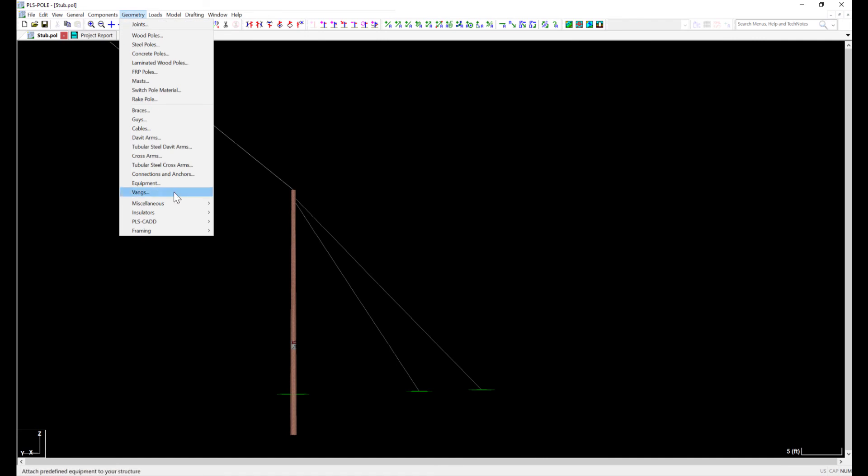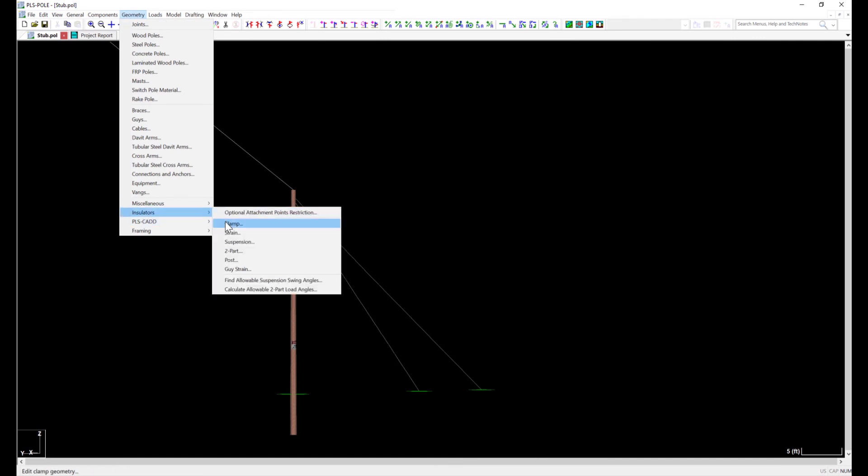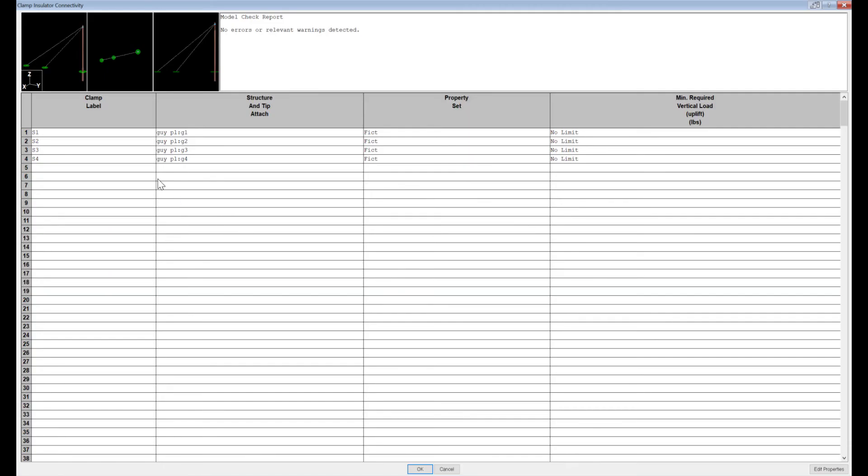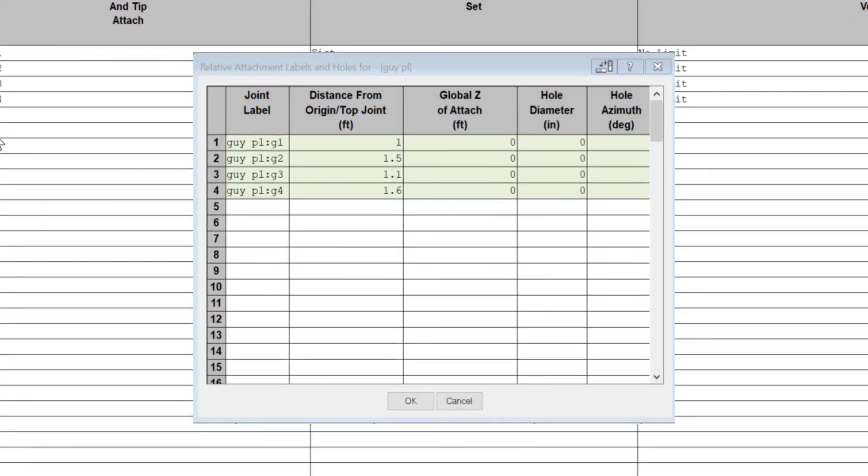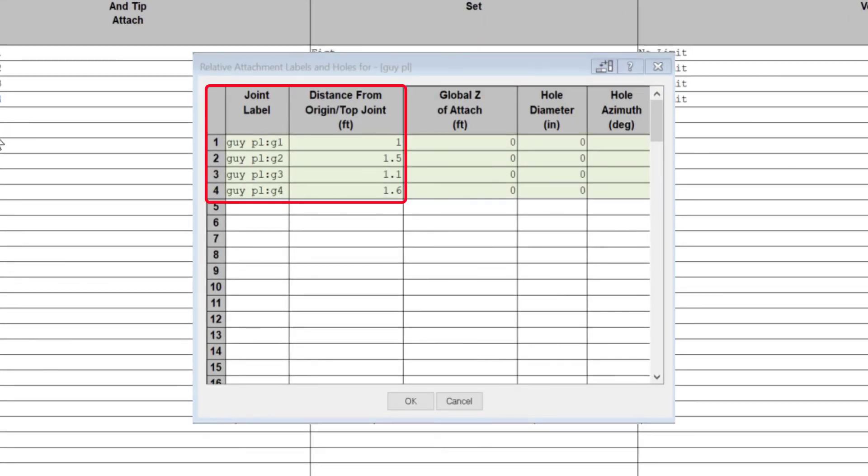Again, I navigate to Geometry, Insulators, Clamps to add my clamps to my previously created attachment points. You can see that I have 4 clamps attached to this pole. Clamps are unique in that I cannot add 2 of them to the same attachment point. For this situation, I simply added another attachment point at a distance of 0.1 feet away from the other attachment points.